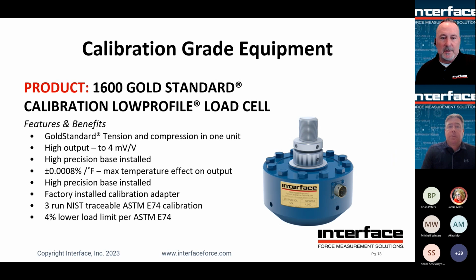Here's an example of our 1600 series gold standard load cell. Very high accuracy, it has a high output of 4 millivolts per volt, and a precision base installed. It has a factory installed thread adapter. The thread adapter you see on the top of the load cell is installed at the factory and is meant to stay in place. That helps achieve a higher degree of accuracy versus a customer installing their own thread adapters. A sensor like this can be used in tension and compression and has a 4% lower load limit.